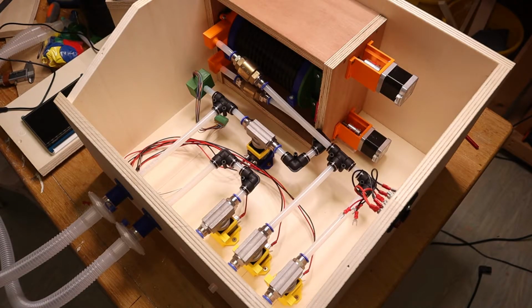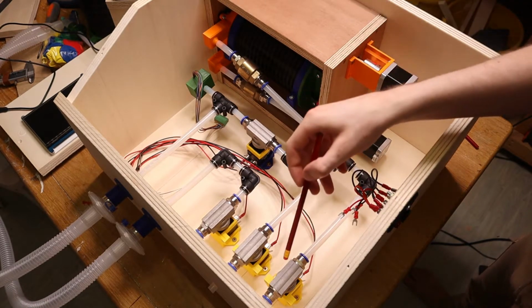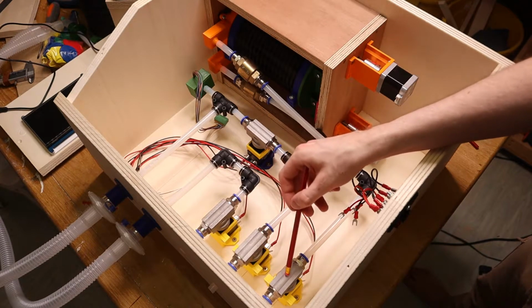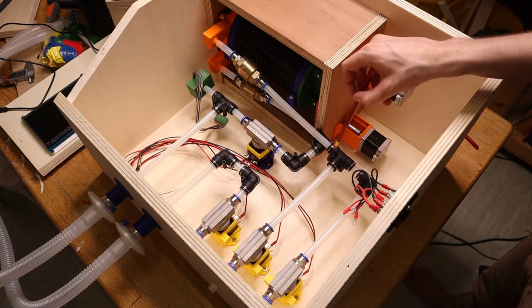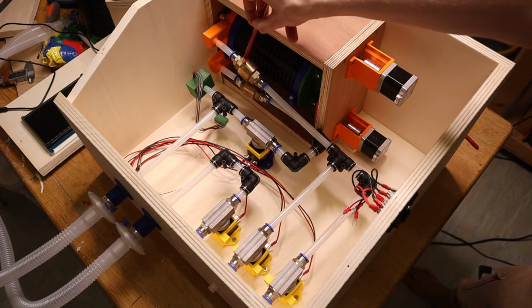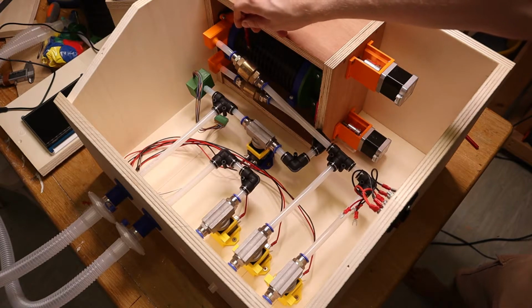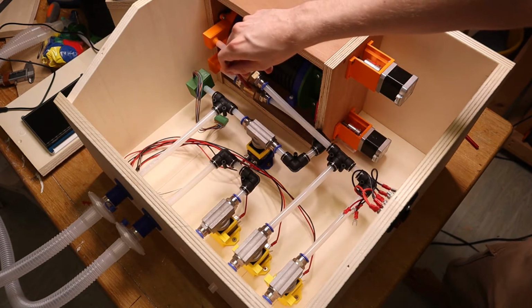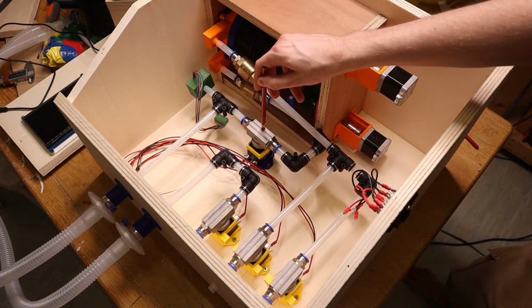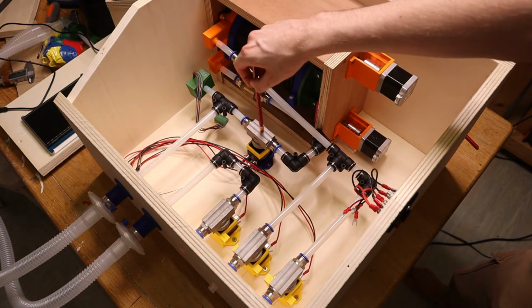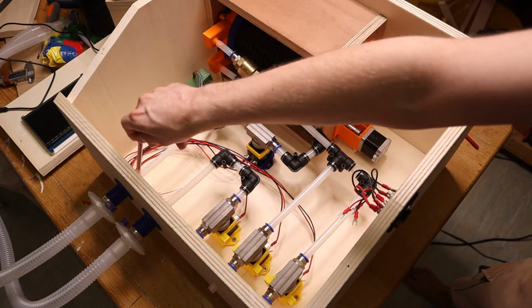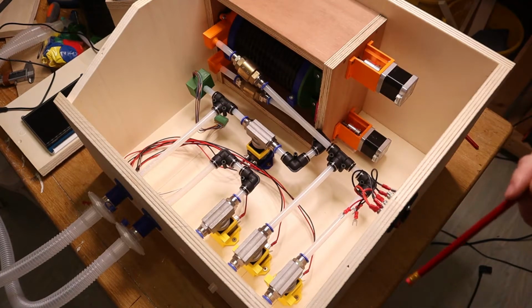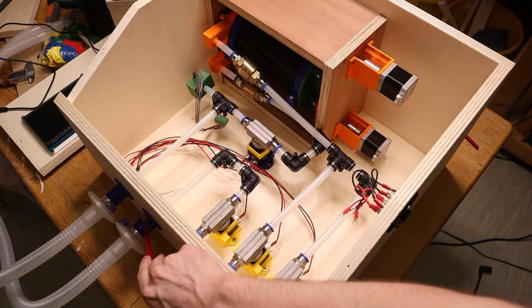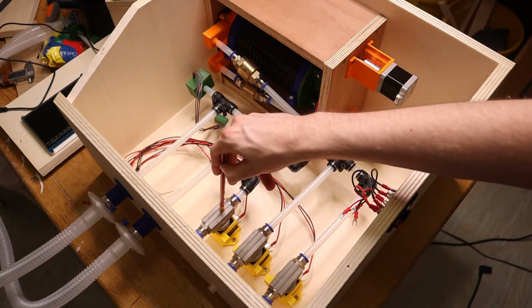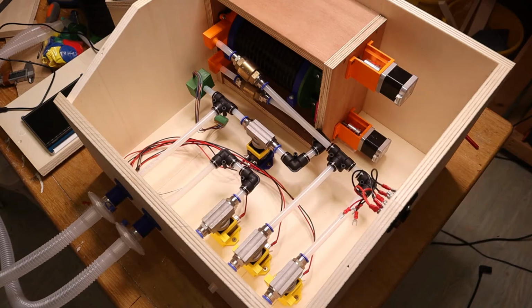I've now removed the electronics section so that we can get a better look at the tubing and the valves below. So starting here on the right, we have the oxygen and air inputs solenoid valves. And these two lines come together in this T-piece, and then they go through the one-way check valve into the bellows pump. And then from the bellows pump we go through the other check valve via these angles into the inspiratory solenoid valve, and then through the T-piece out of the machine and into the patient. And then from the patient it returns through the other line, and then it just goes through this solenoid valve over here and the air comes out.